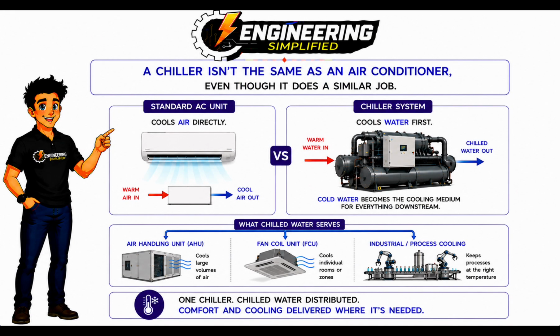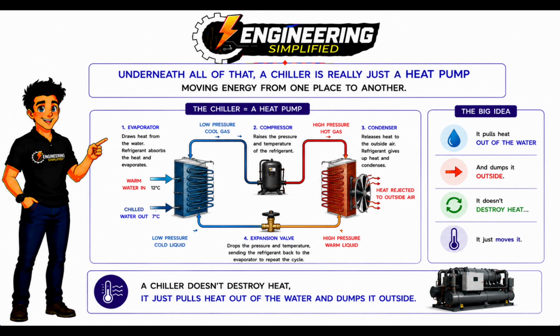A chiller isn't the same as an air conditioner, even though it does a similar job. A standard AC unit cools air directly. A chiller cools water first, and that cold water becomes the cooling medium for everything downstream, whether that's an air handling unit, a fan coil, or a production line. Underneath all of that, a chiller is really just a heat pump moving energy from one place to another. It doesn't destroy heat, it just pulls heat out of the water and dumps it outside.